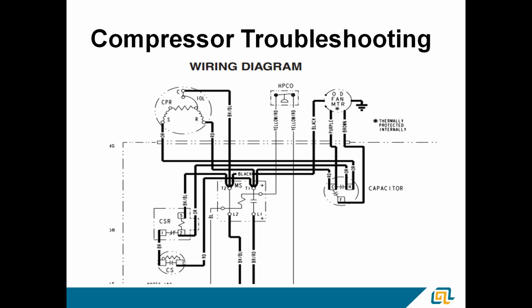And honestly, the same thing will happen if your fuse on line 2 is blown and line 1, the contactor is closed, line 1 is still hot, you're going to get a back feed back to T2. So measuring voltage to ground in this case can be deceiving. You need to go across from T1 to T2. That's where you've got to have your 240 volts.